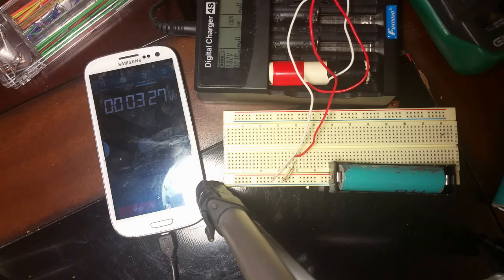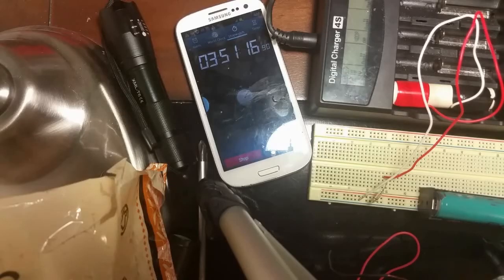For example, these batteries are rated 1C, so I can safely pull 2 amps out of a single battery. But the engineers who put those spec sheets together, their tests may have shown no problem up to 4 amps, and for safety factors, they rate the battery for only 2 amps. Whatever that number is, that's where you want your battery to disconnect from your system if it exceeds that level.